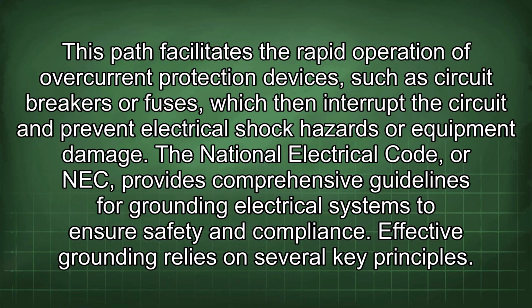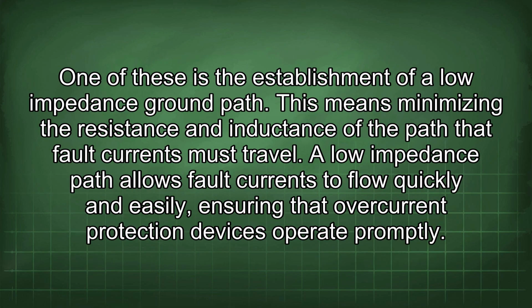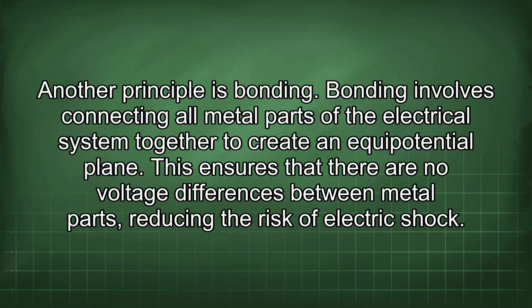Effective grounding relies on several key principles. One of these is the establishment of a low impedance ground path. This means minimizing the resistance and inductance of the path that fault currents must travel. A low impedance path allows fault currents to flow quickly and easily, ensuring that overcurrent protection devices operate promptly. Another principle is bonding. Bonding involves connecting all metal parts of the electrical system together to create an equipotential plane. This ensures that there are no voltage differences between metal parts, reducing the risk of electric shock.